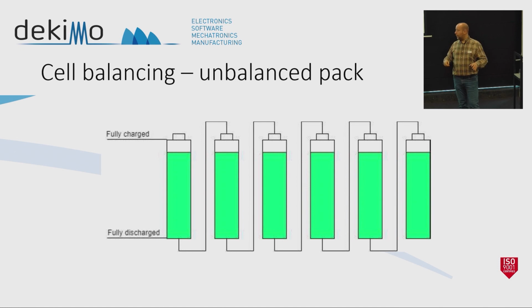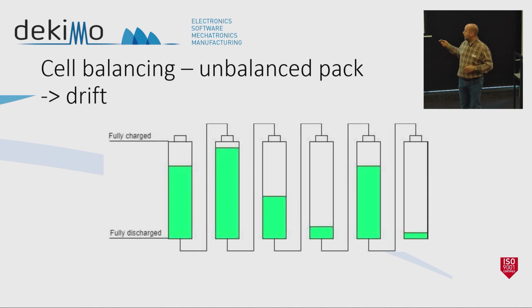But when you discharge this battery, the first battery will discharge to, let's say, 10%. The second will go to 11%, the next to 9%. Let's recharge it again - the battery discharged to 11% will charge back to 100%, but the one discharged to 9% will not reach 100% anymore. This is where you get drift, and at the end your battery pack will look something like this.